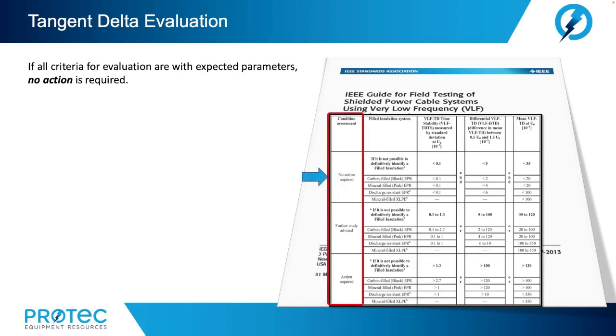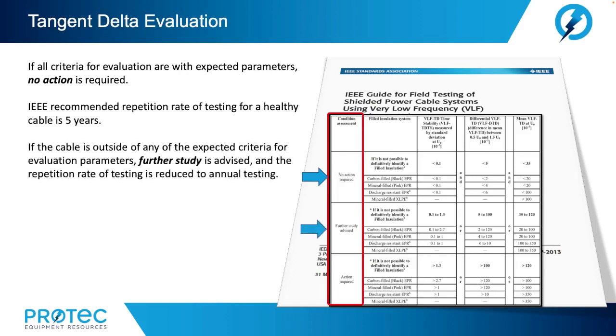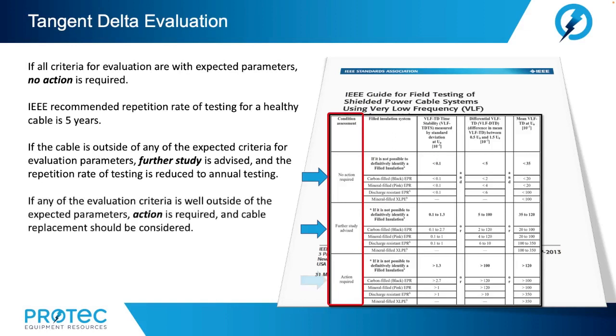If all criteria for evaluation are within the expected parameters, no action is required. IEEE recommended repetition rate of testing for a healthy cable is every 5 years. If the cable is outside of any of the expected criteria for evaluation parameters, further study is advised and the repetition rate of testing is then reduced to annual testing. If any of the evaluation criteria is well outside of the expected parameters, action is required, and cable replacement should be a consideration.